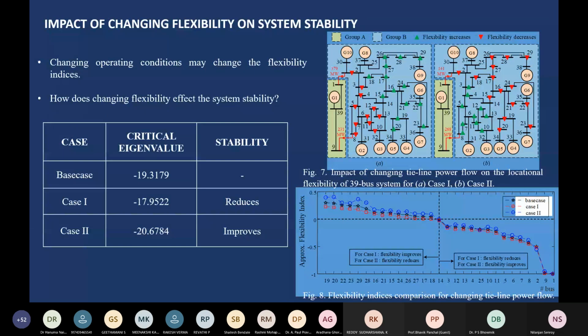So using this flexibility index and the inertial index, we have also analyzed the stability of the system, and we find that changes in the inter-area power flow actually result in buses moving closer to or farther away from the center of inertia. So this way we can define some critical inter-area tie lines, and these tie line power flows can change the spatial inertia in real time in the system. Remember, the physical inertia is located in the same place, it does not change. However, the distribution of that inertia across the entire network is affected by the power flows on critical tie lines. Not all tie lines, but the critical tie lines. These are the tie lines that are connecting coherent groups of generators.